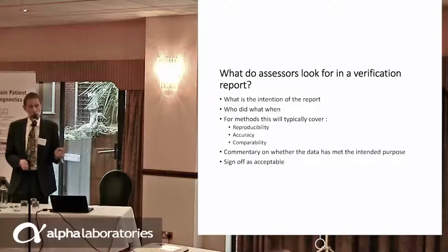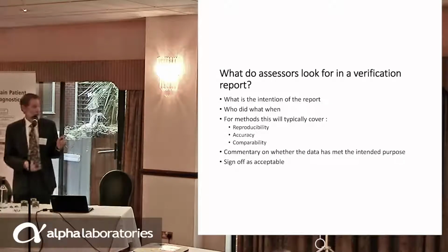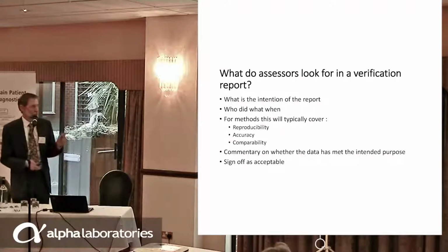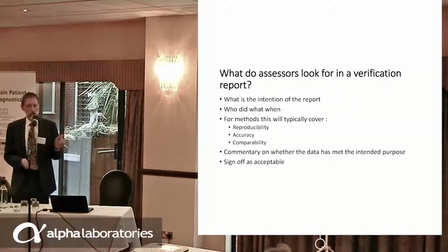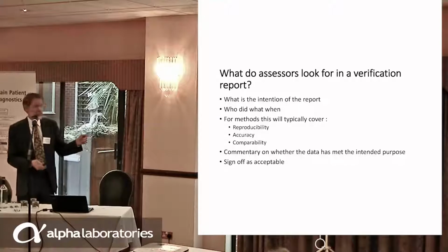So what am I looking for when I look at a verification report? I'm looking for what was the intention of the report, what's it verifying? Is it the temperature monitoring system that you're verifying? Is it a urea method that you're verifying? You need to say who did what when, okay? Because quite often I've seen verification reports that have nobody's name on them, and they don't say when it was done. It could have been last week, it could have been 5 years ago.